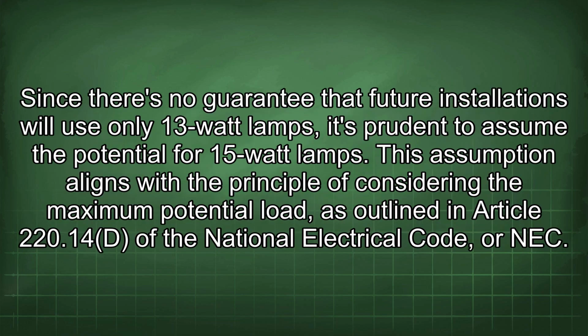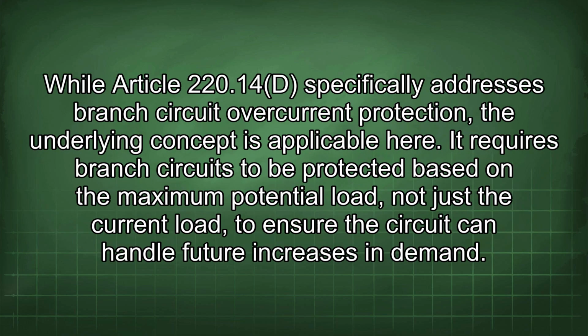Since there's no guarantee that future installations will use only 13-watt lamps, it's prudent to assume the potential for 15-watt lamps. This assumption aligns with the principle of considering the maximum potential load, as outlined in Article 220.14(D) of the National Electrical Code, or NEC. While Article 220.14(D) specifically addresses branch circuit overcurrent protection, the underlying concept is applicable here. It requires branch circuits to be protected based on the maximum potential load, not just the current load, to ensure the circuit can handle future increases in demand.